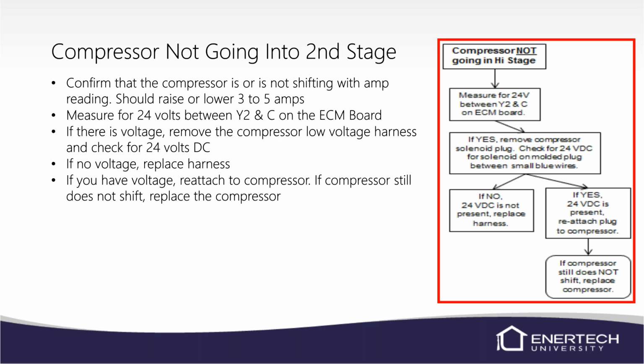If you do have voltage there on the ECM board, you can remove the compressor low voltage harness. It'll have 2 blue wires on it. That's going to indicate the low voltage harness. You can remove it and check that plug. Now that plug, it's AC voltage coming into it and DC voltage out of the plug to the compressor. So if your meter switches from AC to DC automatically, you won't even really notice it. But if you have a meter that you need to switch, then you have to switch it to DC.